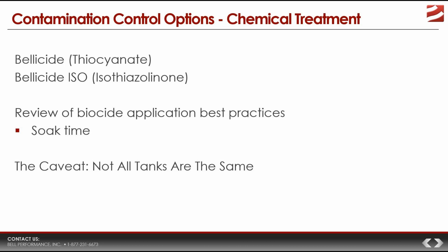Now, that's an important thing. You have to start by having an actual effective biocide chemistry. Once you have that, you need to use it properly. Biocides need time to work, and that period of time is typically what's referred to as a soak time. Now, how much soak time do they need? Well, if you ask the fuel microbiologist, he would say 24 to 48 hours is an optimal soak time. If you're a fuel service company, you may not be able to wait 24 to 48 hours, but if at all possible, that is your optimal window.